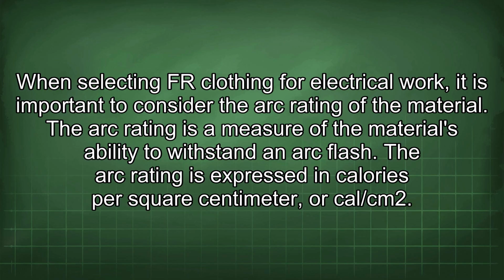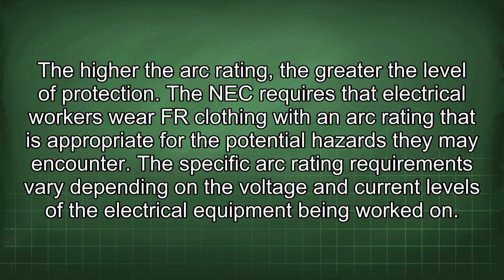When selecting FR clothing for electrical work, it is important to consider the arc rating of the material. The arc rating is a measure of the material's ability to withstand an arc flash. The arc rating is expressed in calories per square centimeter, or cal/cm2. The higher the arc rating, the greater the level of protection.